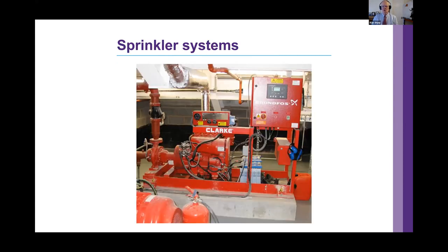Here we've got a sprinkler system actually powered by a small diesel engine, and the fire water is pumped to feed sprinklers directly or to fill a header tank. The system can be pressurised manually or automatically in the event of a fire alarm, and the sprinkler heads are actuated by heat at different temperatures. Note that fire standards often change — fire precaution principles and practices are updated all the time, so check with your fire safety advisor if in any doubt.